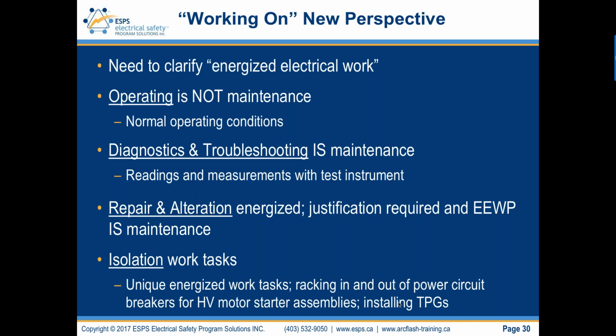This next slide, to keep things moving, is clarifying working on. So I said earlier that operating needs to be clarified. Operating energized electrical equipment is not maintenance. Under normal operating conditions, we don't need arc flash or shock PPE to be worn by workers that are authorized to operate. This includes isolation, opening and closing of circuit breakers and disconnect switches, or having contactors open and close while we're standing in front of motor control centers. This is where the huge debate occurs. So I'm going to make some statements, and if you want, you can contact me after the webinar, and we can discuss them further.